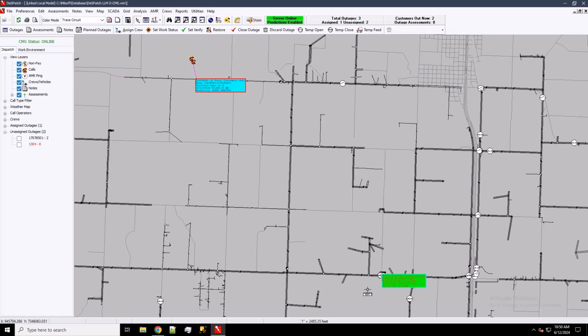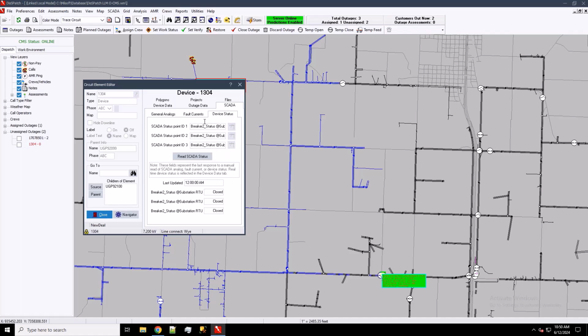One other thing I didn't mention earlier, but is probably worth mentioning now, is that our default prediction engine setting is that if we define a device as having a SCADA device status point, we take this device out of our normal prediction routine, meaning we won't predict an outage to this feeder breaker when calls come in downline. By default, we expect the SCADA integration to control and tell us when this device is open or closed. Now, if I have a different feeder that doesn't have SCADA configured, I won't have the point IDs, and we could take enough calls and outage reports to naturally have the prediction algorithm grow an outage upline to that feeder element. But once the SCADA device point is applied, we take that out of the prediction routine. Again, that's a configurable option.